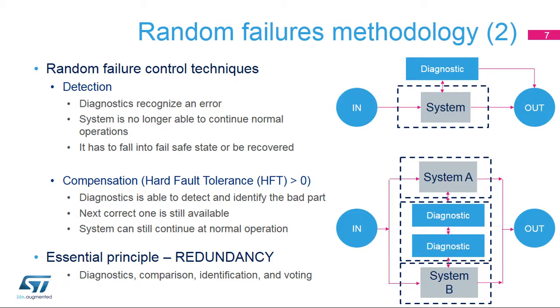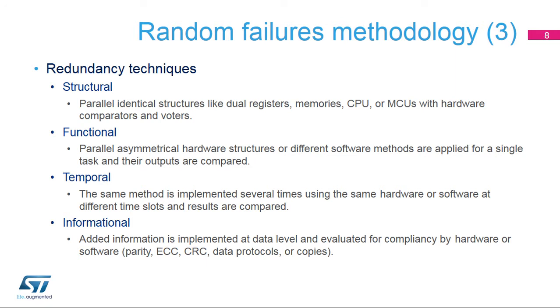Standards recognize hard fault tolerance, or the maximum number of errors which a system can absorb while it still can continue at normal operation. In addition to specific functional testing, redundancy is the essential diagnostic principle. Both detection and compensation techniques always require a certain level of redundancy to be efficient. Compensation is considerably more demanding than detection, as not only discrepancies but the correct state has to be identified as well. To do so, specific comparison and voting mechanisms have to be additionally applied. The required level of redundancy can be achieved using a wide range of different software or hardware methods and techniques.